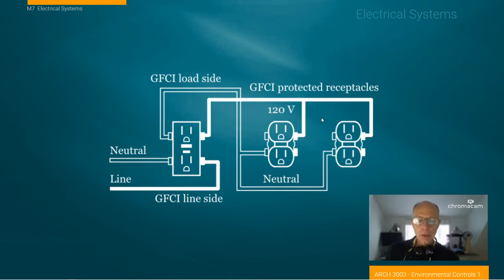It's important to note that you only need one ground fault circuit interrupter per protected series of outlets. So in a kitchen, you can have, if you need two branch circuits, two 20 amp circuits, you would only need two ground fault circuit interrupters. And then it's the first one in the line. And then everyone that comes off of that branch circuit can be a standard outlet. This ground fault circuit interrupter will protect any outlet downstream of the supply.